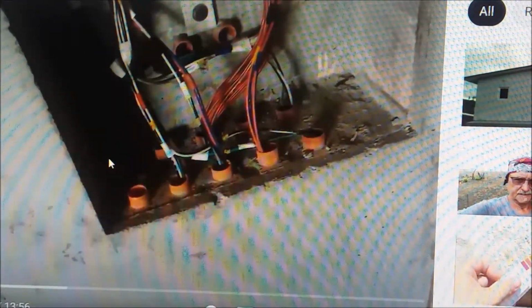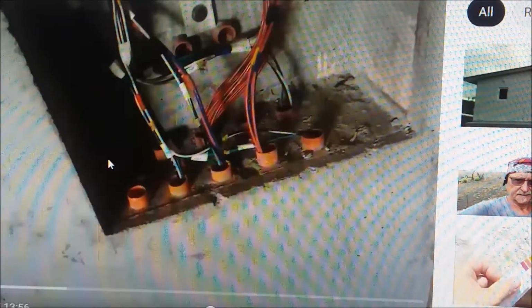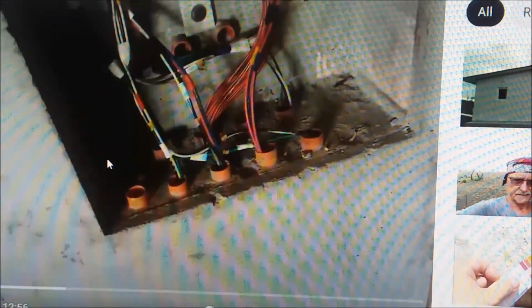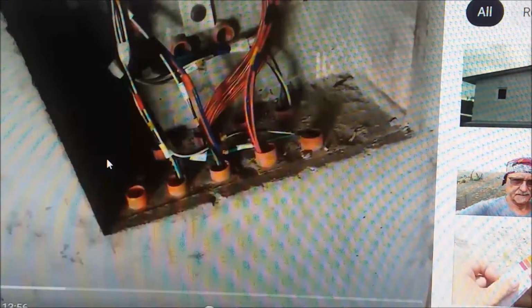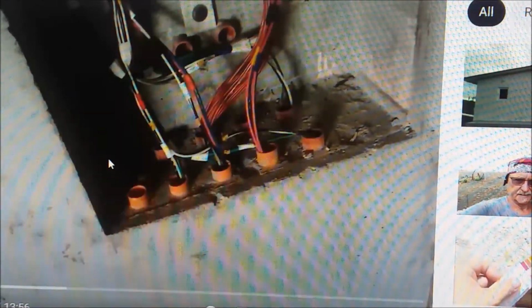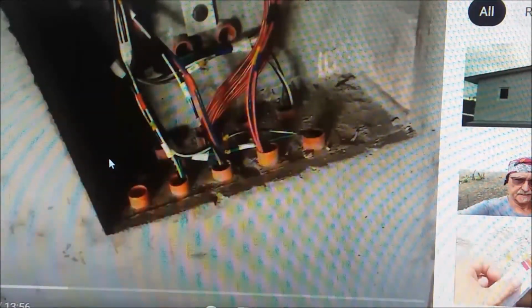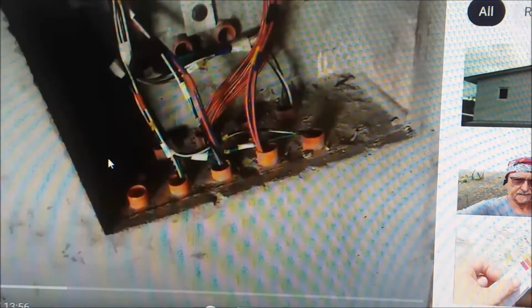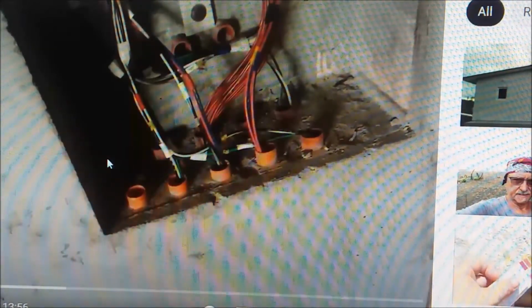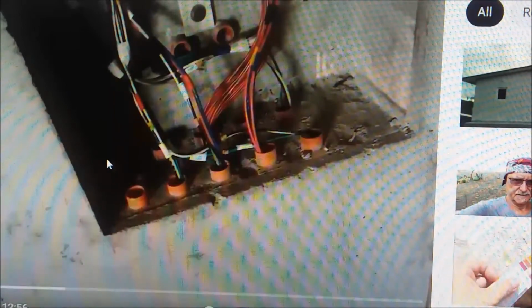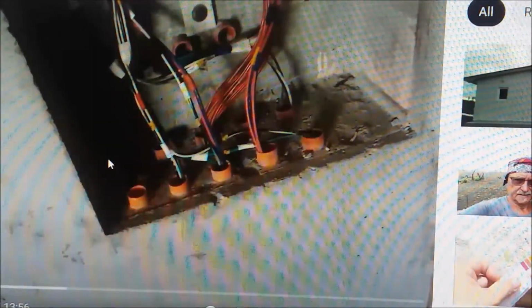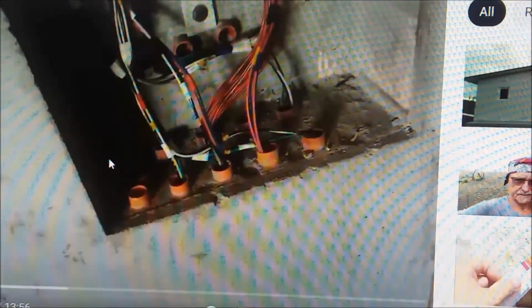Because somebody's going to turn that breaker back on right when it's in transition temperature, and then it'll never work again. It's like motor starters in industry—they work by melting solder. It gets so hot the solder melts, a shaft slips through a hole, a gear turns, and it lets a little arm out and drops the power, shutting all 3 legs off.